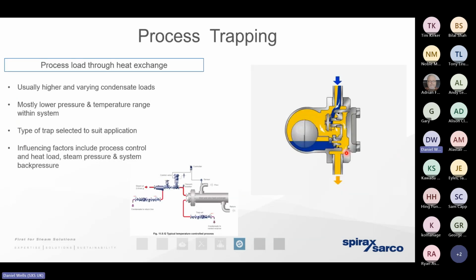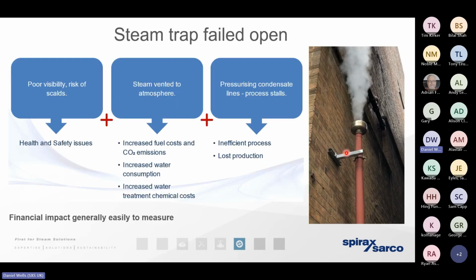So, of course, wherever we're using steam for heat exchange purposes, we need to remove the condensate. We're going to be removing a much greater mass of condensate than the condensate that exists in the distribution pipework. But that condensate is going to exist at a lower pressure and lower temperature. But it's still vitally important that we get the condensate away. But it really reminds us that we're going to need a completely different size and a completely different type of steam trap in order to fulfill that purpose.